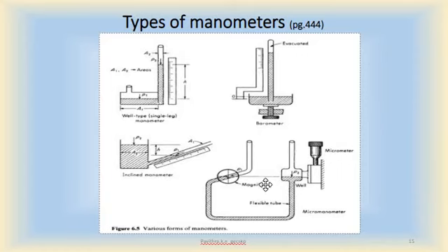So here we are maintaining the levels P1 and P2 at the same level, and the meniscus at this point of this inclined tube is located at a reference point given by a fixed hairline viewed through a magnifier. By viewing through a magnifier, we are fixing the level of the fluid at a particular point. So here the reading of the micrometer is used to adjust the well height. That is why it will be more accurate.